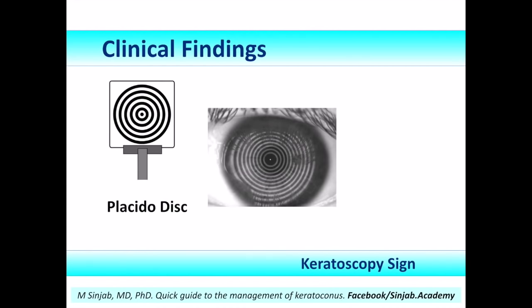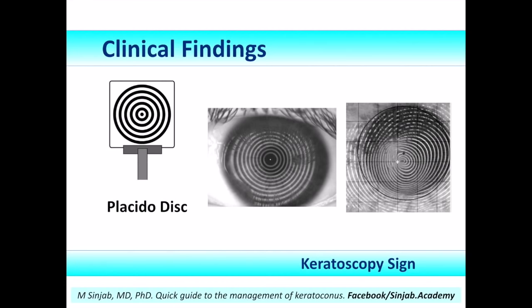The keratoscopy sign: the Placido disk is used to detect the shape of the anterior surface of the cornea. The rings of the Placido disk are projected onto the surface of the cornea, and the first Purkinje image of these rings reflects the shape of this surface. As we see in the image in the middle, the rings are concentric, central, and regular, reflecting a normal cornea. While in the image on the right, the cornea is distorted — the rings are crowded in some places and separated in others, reflecting the anterior surface of a keratoconic cornea.